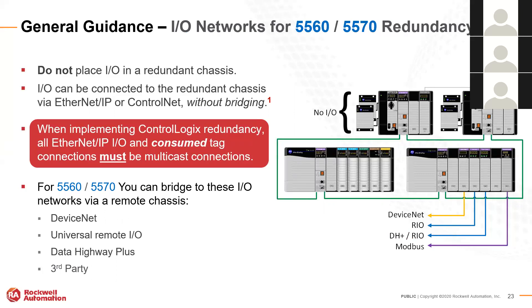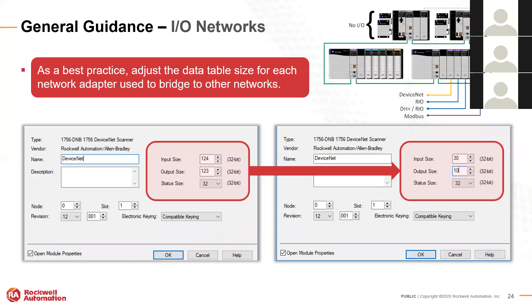With the 5570, we still support DeviceNet, ControlNet, and Modbus — but comms cards other than ethernet cards are never placed in the controller chassis. If supporting Modbus, ControlNet, or DeviceNet, those cards go in the IO chassis. Those rules haven't changed. Also always configure your different networks like DeviceNet or ControlNet for the actual data you're moving — don't leave them at defaults, as that can slow down data and create issues.